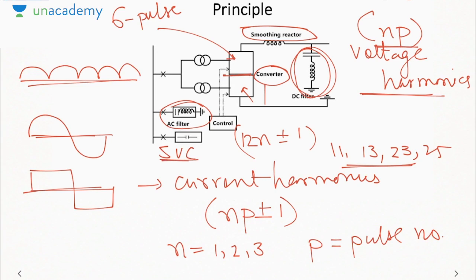This is your SVC or static VAR compensator. Why is it used? See, in case of rectifier, due to harmonics, the power factor is less. Okay, so what happens on the DC side, there is no concept of reactive power, so the entire reactive power required by the converter will be supplied by the AC side. That is why the power factor will get reduced when we are using a power electronics converter. Power factor is low, so we need to increase the power factor, and that is done by means of an SVC, that is a static VAR compensator. So we need to use reactive power compensation on the AC side in case of a power electronics converter, otherwise power factor would be low.